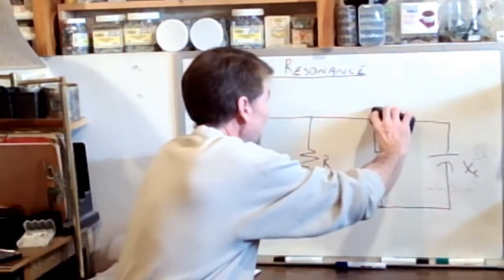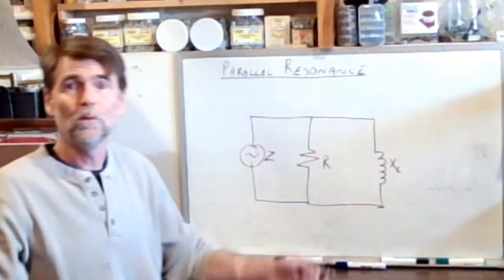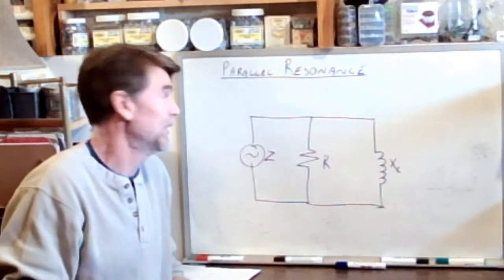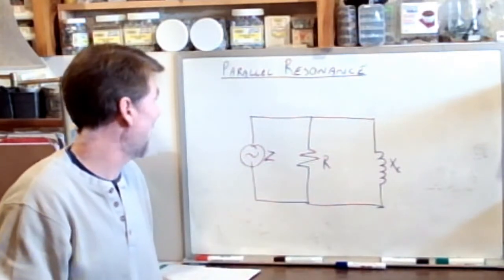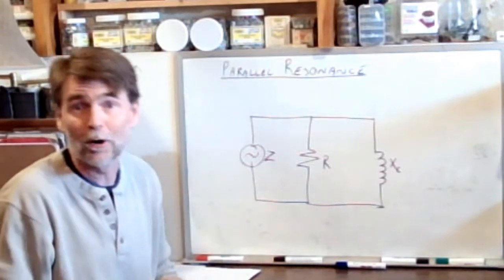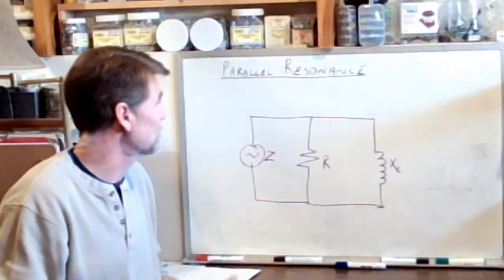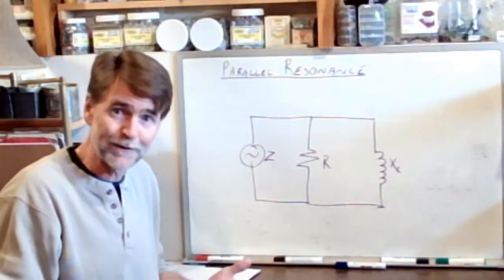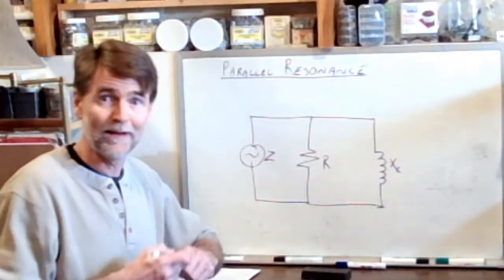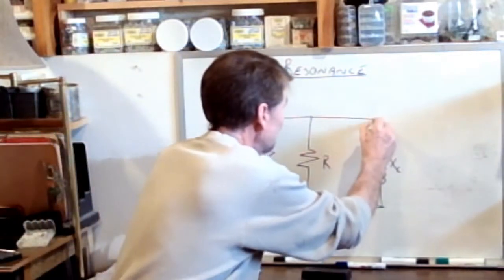Okay, so if I back up just a little bit and we eliminate this branch, here we go. We now have a circuit which is doing some work. We have a motor in our circuit, and we probably have a really terrible power factor, okay, 0.3 or 0.4 perhaps. And so in order to correct for that, we add to our circuit in parallel a capacitor.